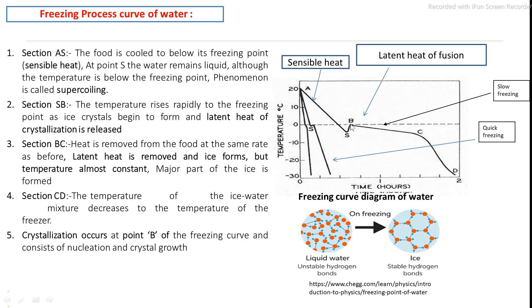The temperature slightly drops below 0 degrees Celsius, then rises back up to the freezing point where nucleation starts. After nucleation occurs, crystals begin to grow — this is the crystal growth process up to point C. After point C, the temperature is again reduced to the internal storage temperature of the frozen storage room. The main steps are: removal of sensible heat, nucleation, crystal growth, then final temperature reduction.